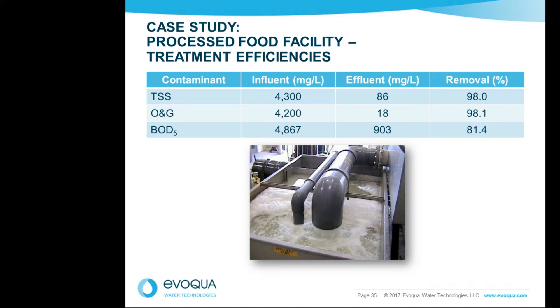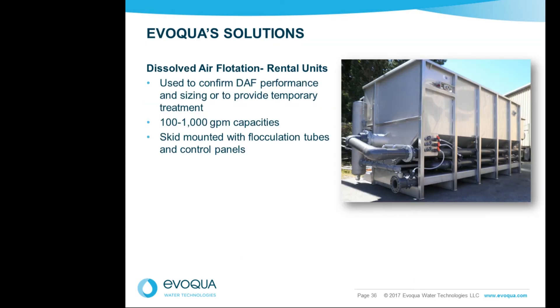The performance results for this Texas facility show that TSS and oil and grease concentrations coming out are fairly typical — TSS is less than 100 mg/L and oil and grease is less than 20 mg/L. Removal percentages are greater than 90% for both suspended solids and oil and grease, partly due to the high influent concentrations. BOD removals are also quite high at 80%, which occurs here because the suspended solids and oil and grease make up a majority of the BOD concentration in the wastewater.